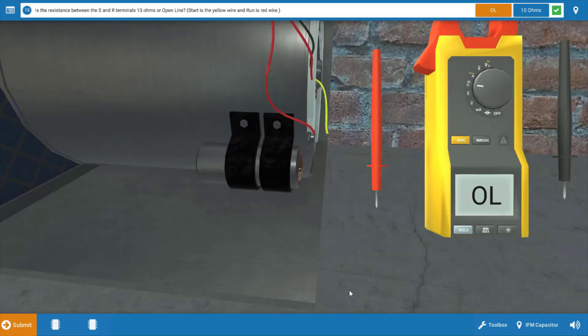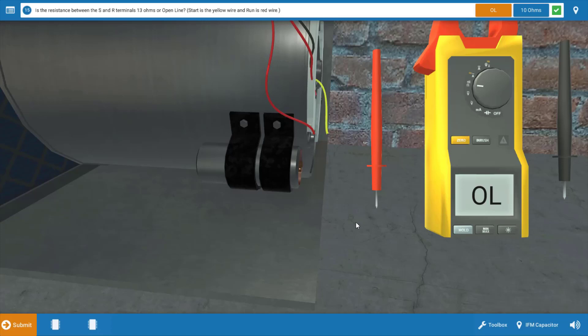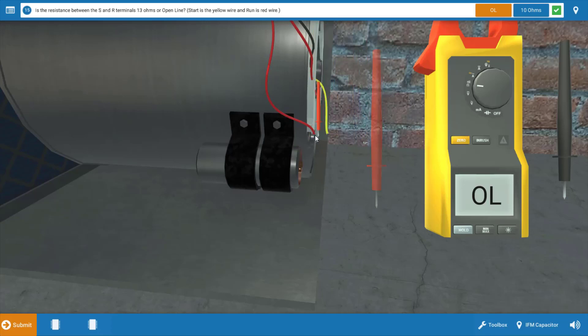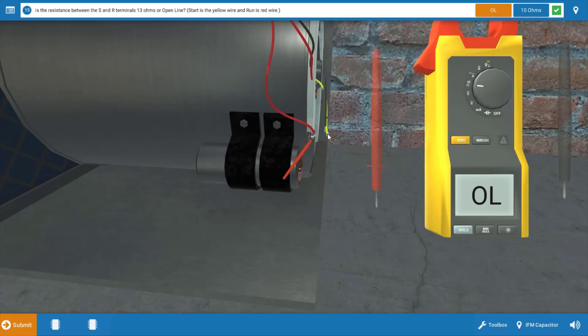Our next step is to measure the resistance of the indoor fan motor windings. You can measure the winding resistances individually. The red wire is our run winding, the black wire here is our common, and the yellow wire is our start winding. But what I'm going to do here is measure across both windings and determine if we have an open circuit or not. We're going to place one of the leads on the red wire and the other lead on the yellow wire. This will measure across both windings.